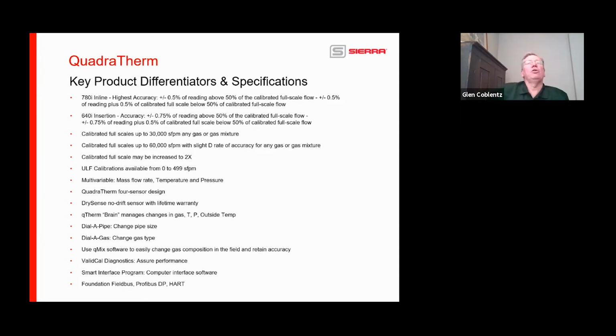What I mean is, let's say you have a customer with a compressed air line. They put the meter in the line, and it's calibrated 0 to 1,000 SCFM, and let's say the equivalent is 10,000 standard feet per minute. An engineer made a mistake somewhere, and they really need 2,000 SCFM. Not a problem. You can go into the full scale and up it to 2,000 SCFM. Is your accuracy still going to be 0.75% of reading and 0.5% below 50%? Probably not. It's probably going to be 1 to 2% of full scale, but you just saved the day. They don't have to send it back or get it recalibrated, because that was a pretty horrible mistake to miss the full scale calibration by 100%. So that gives you a 2x in the field.